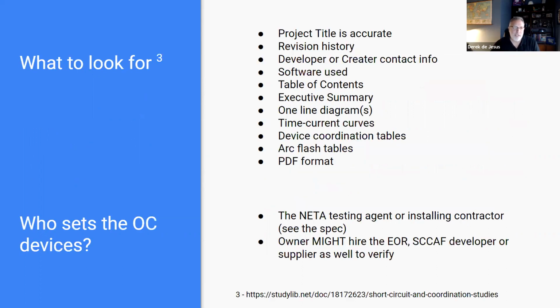So what to look for? What to look for in this report? So now you're not necessarily just commissioning a mechanical piece of equipment, going to look at the SCCAF report. I understand that you're just going to be looking for the arc flash label, verifying that your equipment is being fed. But if you do have electrical commissioning as part of your scope, you want to treat the SCCAF report much like you would a TAB report or a NETA testing report, right?